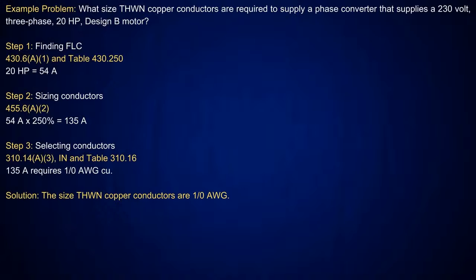conductors, usually, I have a rule of thumb where I say if you size an overcurrent device at 125% or less, you go up to the next standard size. Any percentage above that, you drop down unless it states otherwise. And I give you 2 instances when I give that rule of thumb. I said you really have to look at phase conversion because it tells you it has to protect the conductors. And in this case, they have them going up to 250%, which is 135 amps, which requires a 1-aught conductor in the 75 C column, which is good for 150 amps. But when I size the overcurrent device, instead of dropping down, I would put a 150 amp overcurrent device there, because in this section, it tells you have to protect the conductor.